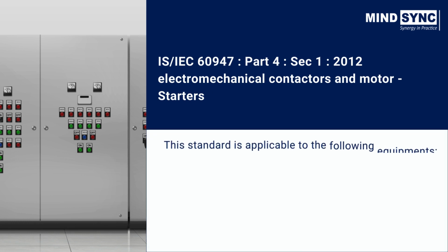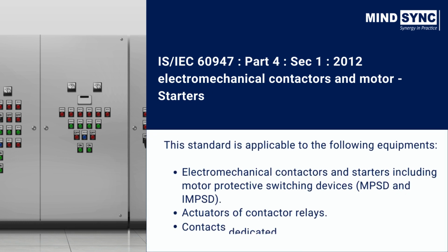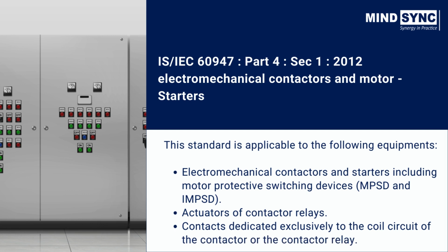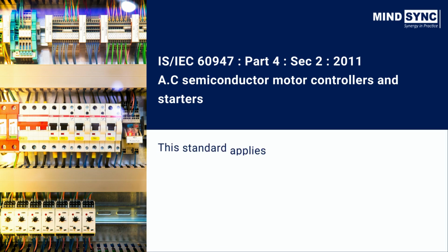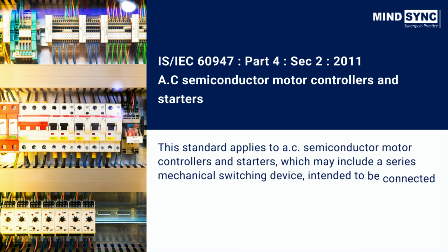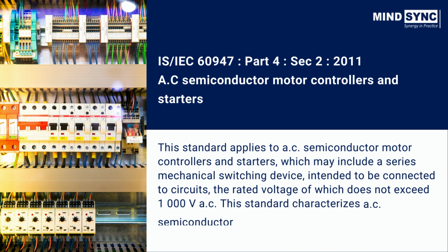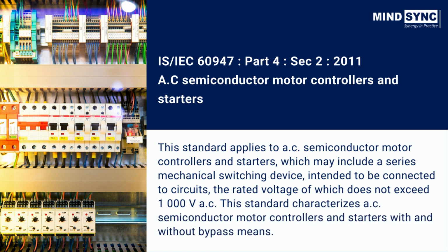Moving on to the third standard, it focuses on electromechanical contactors and motor starters, encompassing various equipment such as electromechanical contactors, starters, motor protective switching devices, actuators of contactor relays, and contacts dedicated exclusively to the coil circuit of the contactor or contactor relay. The fourth standard addresses AC semiconductor motor controllers and starters, applicable to controllers and starters incorporating a series mechanical switching device, intended for circuits with a rated voltage not exceeding 1000 volts AC. The standard characterizes AC semiconductor motor controllers and starters with and without bypass means.